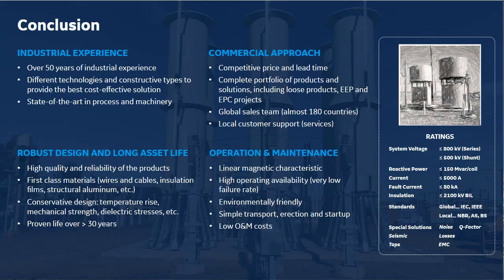Reactors are designed to meet a thermal temperature based on the insulation material that I mentioned before. For example, class F, 155 degrees would be the maximum hotspot temperature. So what we recommend is, by knowing the load of the reactor, because it may not be working on the nominal load, you get a snapshot of the load, make a thermal scan of the reactor if it's in operation, connected, send to the supplier the thermal scan and the load, and we will be able to calculate and see if the reactors are healthy. Now, if the reactors are not energized, you can disconnect and ground it from the system, and then measure the inductance and the impedance of that reactor and compare it to the test reports. That will tell you if there is internal failure and if the winding is still in good condition.